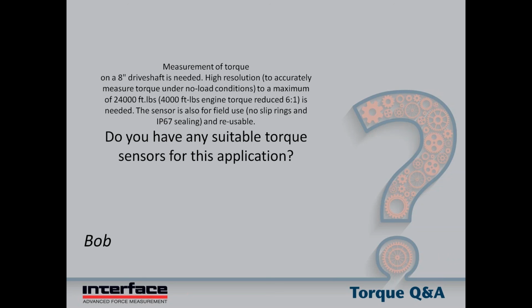Battery-powered telemetry sometimes is quite useful in these types of situations. So there are typically certain reaction-type torque sensors that could be coupled in, but then a battery-powered telemetry system can be added, and that basically broadcasts the data without requiring a closely coupled induction power transfer system. Other cases, the sensor or the shaft just has to be strain gauged and telemetry is applied. Interface doesn't get into strain gauging of shafts. We have a limited ability to provide battery-powered induction systems. So it's something we could talk about, but typically these are difficult applications that I don't necessarily have a great answer for. Okay.